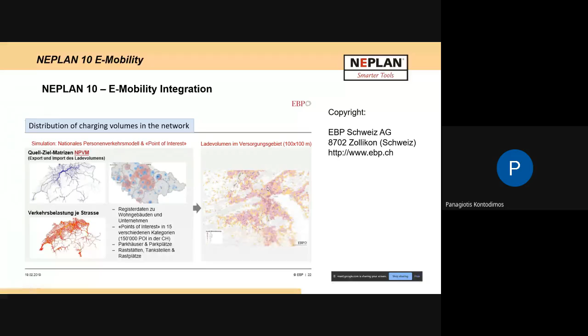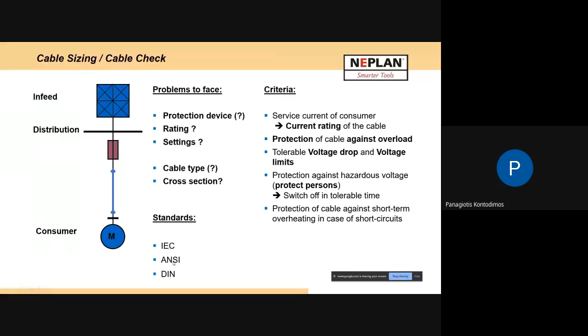For industrial applications, we have cable size and cable check, where we can size cables to meet certain criteria, such as current rating, protection, protection against hazardous voltage, and protection against overheating. The software suggests the cable based on the load in order to pass all these criteria, according to standards like IEC, ANSI, DIN, and so on.